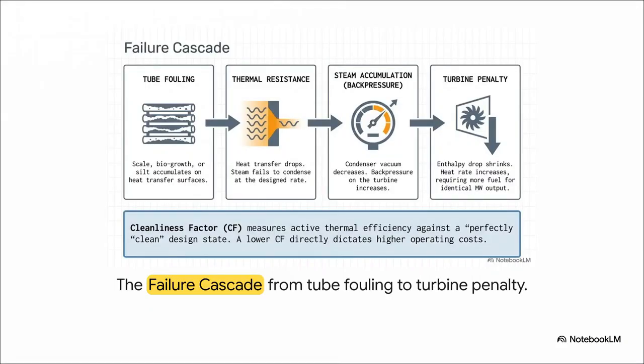Because honestly, things absolutely do go wrong. The failure cascade all starts over on the left with tube fouling. We're talking microscopic scale, biogrowth, maybe some silt building up on those heat transfer surfaces. It's kind of like plaque in an artery. That buildup creates thermal resistance, meaning the heat transfer drops and the steam just fails to condense at the designed rate. That leads straight to steam accumulation, which kills our condenser vacuum and actually pushes back pressure onto the turbine.